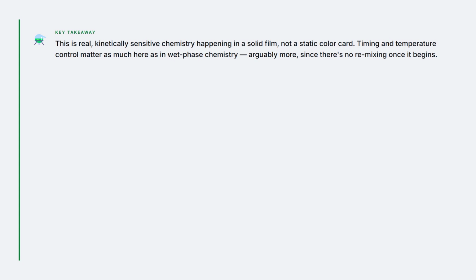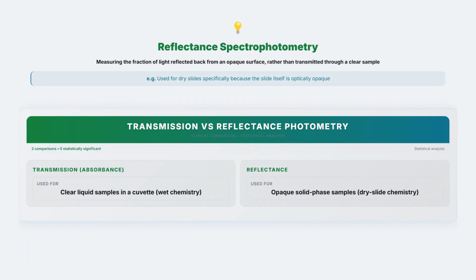Wet chemistry reads absorbance. Light passes straight through a clear liquid sample, and the instrument measures how much light made it out the other side. A dry slide is opaque. Light cannot pass through it at all. So dry chemistry reads reflectance instead. Light shines onto the slide surface, and the instrument measures how much bounces back.